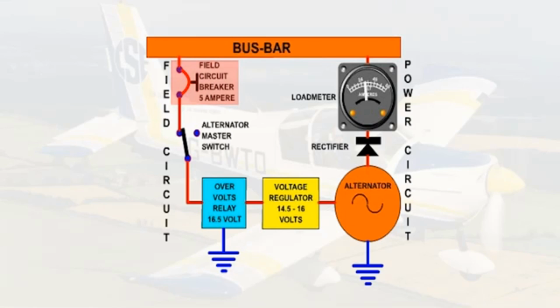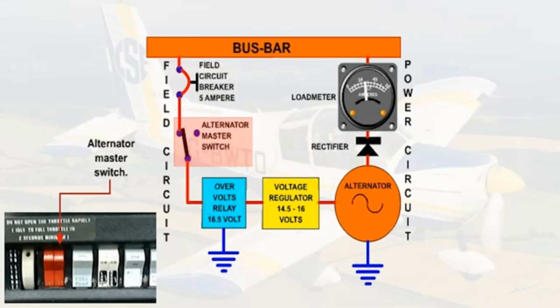The field circuit of this alternator is protected by a 5-amp circuit breaker. Just below that on the diagram is the alternator master switch, which you can see in the photograph is on the left of the row of switches. Immediately adjacent to the alternator master switch is the battery master switch. These two switches are usually mechanically interlocked so that the alternator cannot be operated without the battery. If either the field circuit breaker or the alternator master switch is opened, then the alternator field becomes inoperative and the alternator will not produce any output.